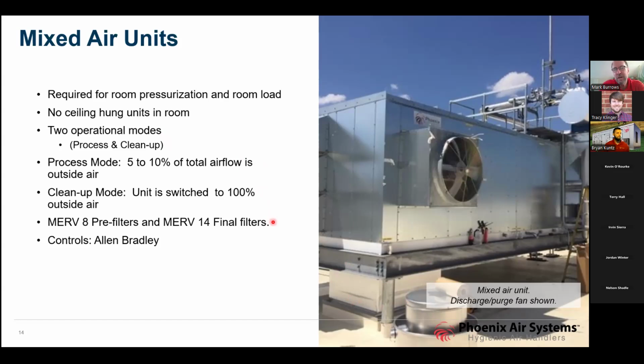If it's basically a cut-up room or on the raw side, you'd be okay with a MERV 14 or 15 at a 95% filter. Again, if you're doing RTE applications, you might want to think in terms of HEPA filters, which are 99.97 effective on a 0.3 micron. As a standard control package, it's going to be Allen Bradley CompactLogix.